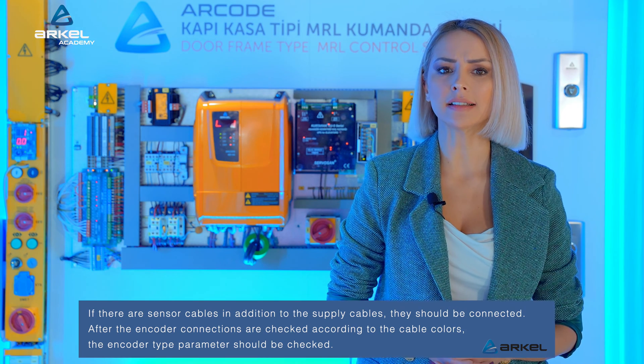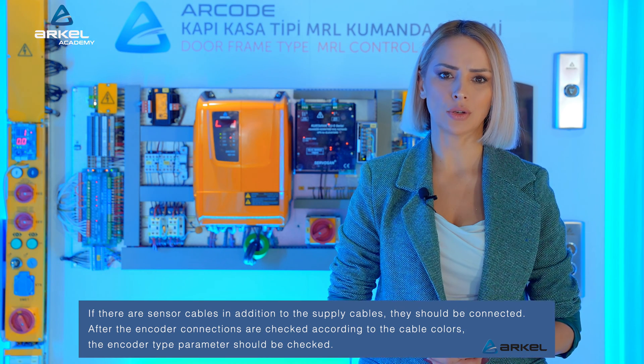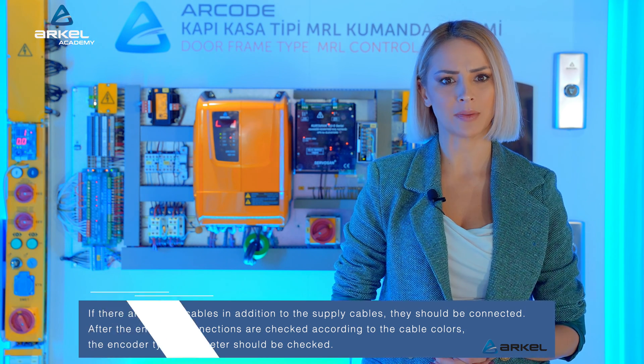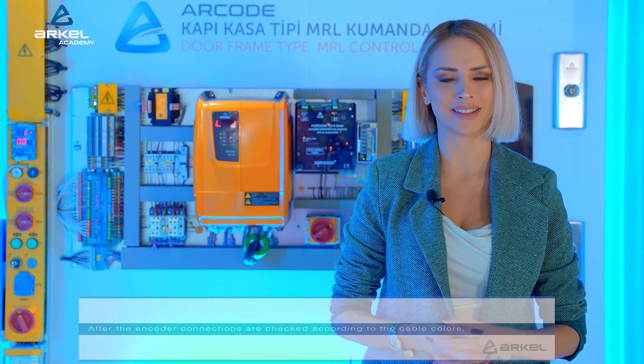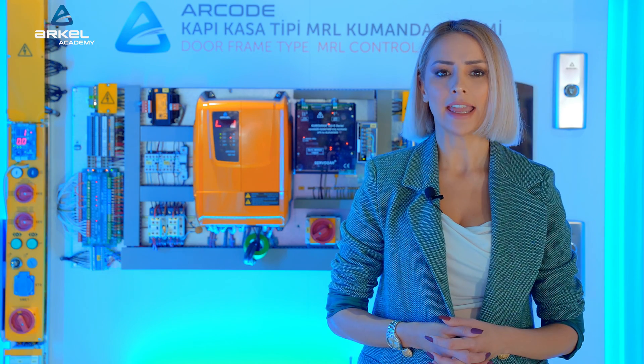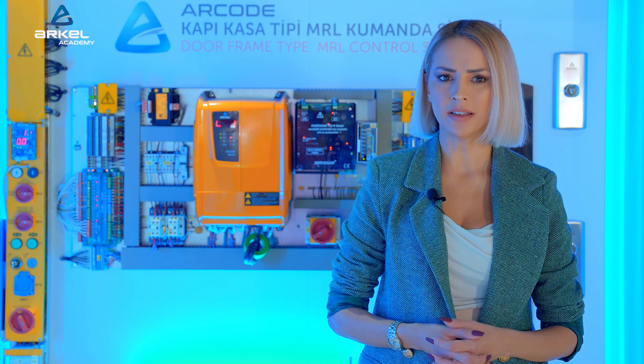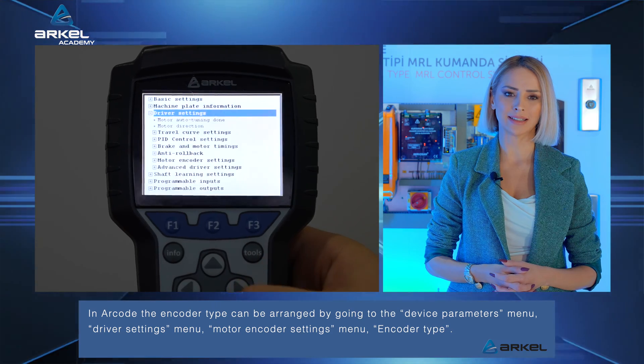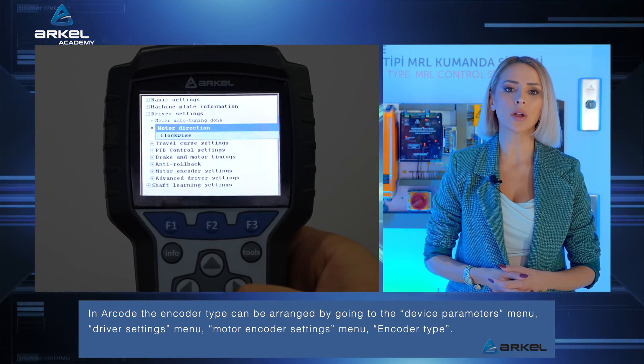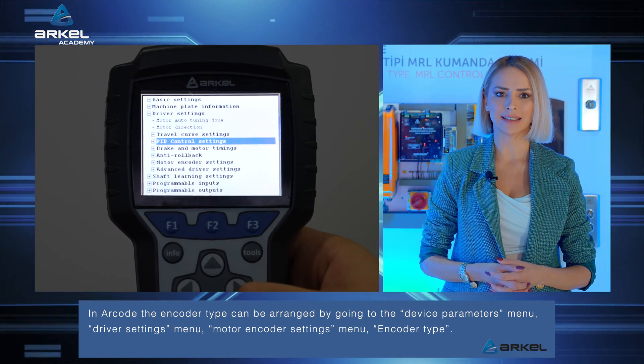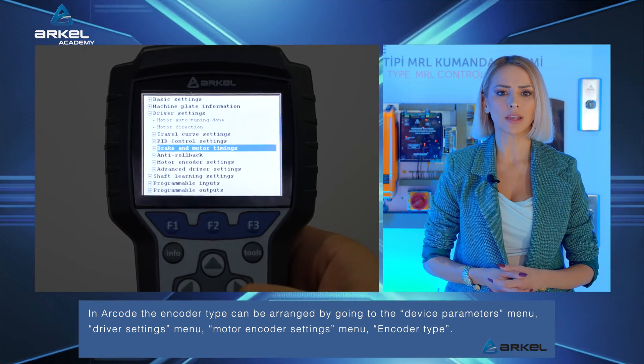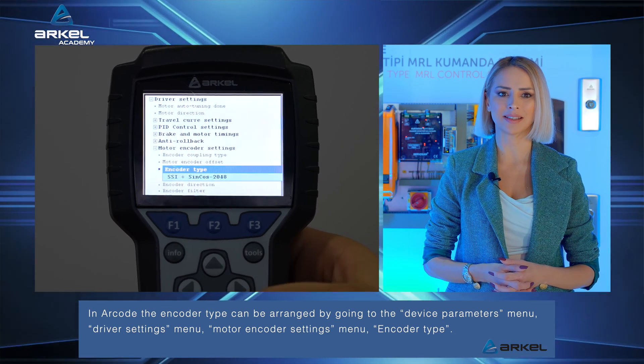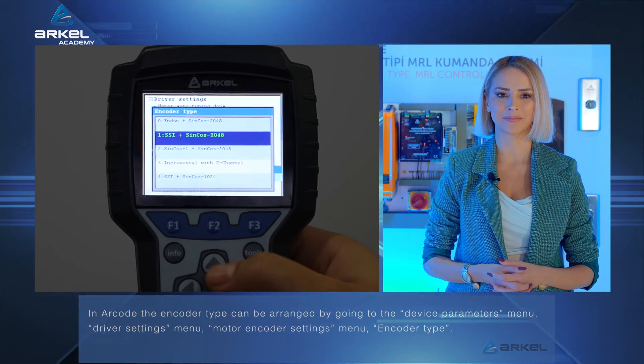After the encoder connections are checked according to the cable colours, the encoder type parameters should be checked. In Arcode, the encoder type can be arranged by going to the device parameters menu, Driver settings menu, Motor encoder settings menu, then Encoder type.